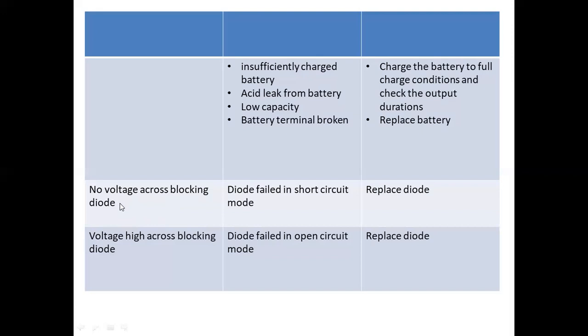From this condition, there is no voltage across the blocking diode. If the diode fails, it becomes short circuit mode. If the voltage is high, it becomes open circuit mode. In both cases — short circuit or open circuit failure — the diode must be replaced.